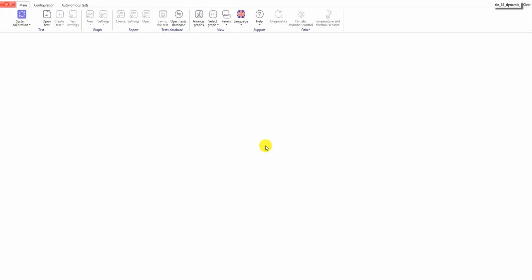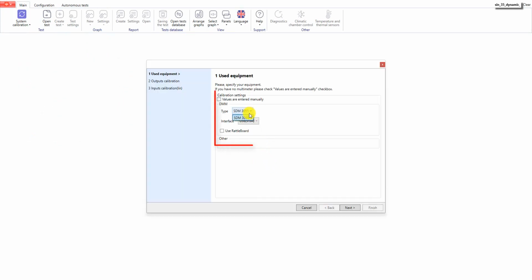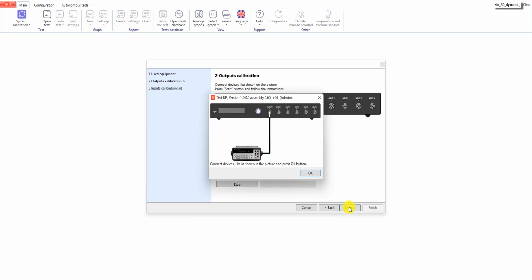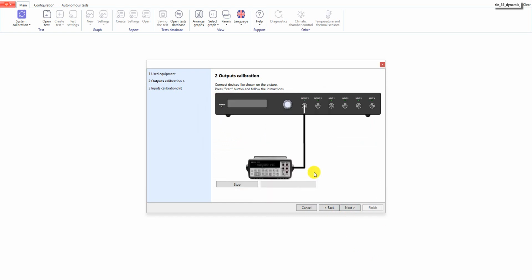So here our first step is the same with the previous calibration. We enter our equipment. We will make all the measurements automatically and we don't have a commutator. Let's press next button. Our first step is to perform outputs calibration. We connect the output of the controller with the multimeter and press OK. Here we'll find the DC and AC shift and compensate it with the coefficients inside the controller.